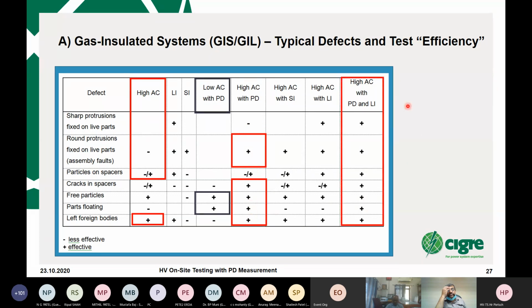And the best way is to combine it with lightning impulse, because with oscillating lightning impulse you can even detect the very sharp protrusions, and this is the best combination. Of course, this is very time consuming. You have accessibility issues and you have to bring an AC source and a lightning impulse generator. As I mentioned, this is only suitable for a very important substation.